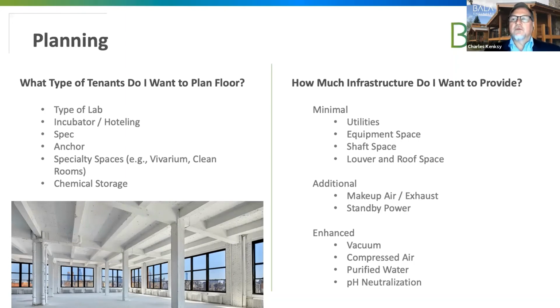So are we bringing the utilities, sizing the chillers and the boilers, getting utilities to the space and stopping, and then the tenant picks it up and puts additional equipment on it? For example, it could be a condenser water system - we bring the condenser water down, and the tenant puts pumps on it, their own water cooled DX equipment, all of this stuff. The delineation of core and shell versus tenant is important to know, because the developer is paying for what we install in the core and shell.